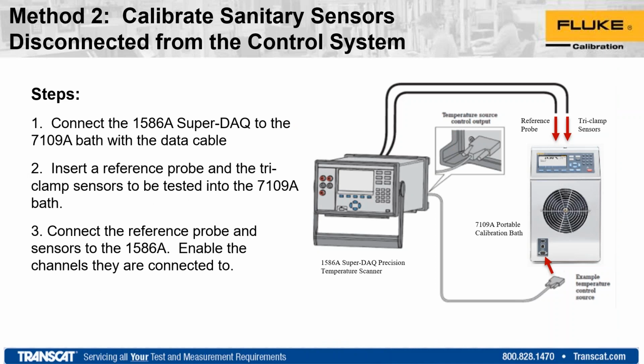All right, so in the next few slides, we're going to talk about that second one, where we've actually pulled the entire sensor itself out of the process. At this point it changes things up because we're no longer using the control room as the verification on the other side for the readout. A couple of benefits to this. A lot of times folks will then perform a calibration on the control panel itself, where they source various resistances, or say millivoltages if you're using a thermocouple, to the board itself to validate that it's also performing. Then you can take the sensor and test it on its own. The reason this is a more enhanced, good method is because you can pick apart what may be causing potential error in the system, whether it's coming from the sensor itself or a potential component issue on the control board.